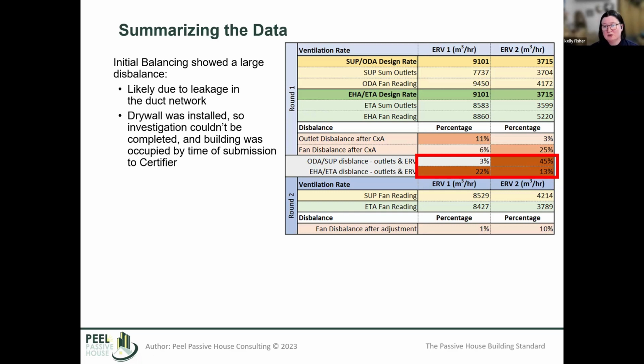But we had a hurdle with this project, and it happened right around COVID, so it was hard to get the information in a timely fashion. The drywall was installed and the finishes were installed. So it was really hard to go back and say, hey, can you try to find the duct leakage that's there, or to remeasure after you've made adjustments, because people were already living in the suites. So understanding the sequencing that you have to do for your duct leakage testing or even your commissioning is very important, so that you still have that time frame to make sure that you can adjust things and investigate if you need to. So with the second round of adjustments, for this particular project, we adjusted it at the ERV itself.